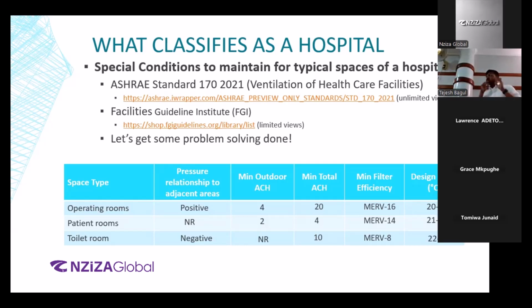Right. Minimum filter efficiency. This is one more thing, and you might have come across this term called HEPA, high efficiency particulate filter. Right. So now HEPA is MERV 17 or above. MERV is minimum efficiency rating value. Now, if you see over here, the operating room, this is the minimum filter value. The more up you go, means you're going better than the minimum, which is always fine. But you need to have MERV-16. But the industry standard will say give a HEPA filter for the AHUs, the air handling units serving the operating room. So more often than not, HEPA filters, MERV 17 or above, will get specified for an operating room.